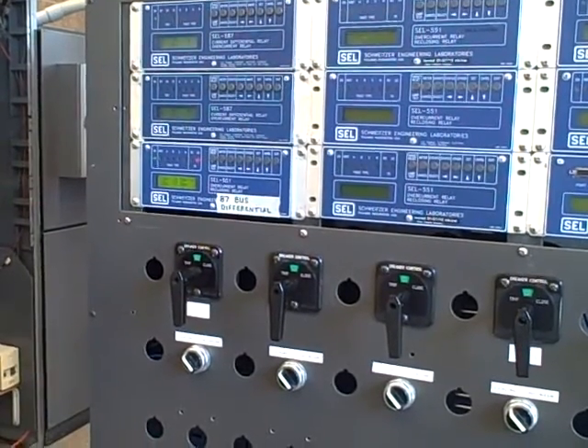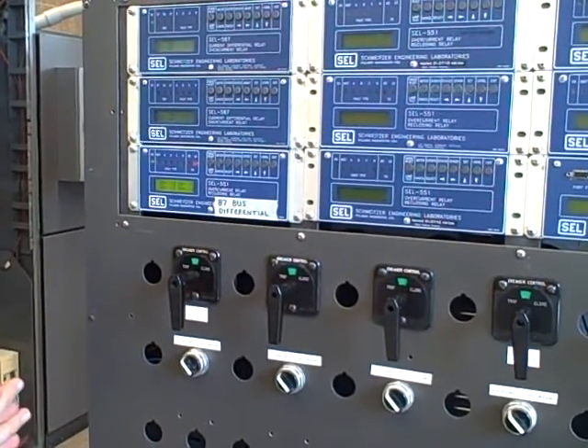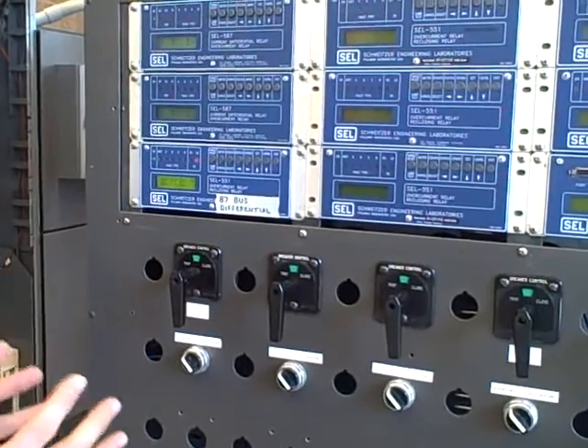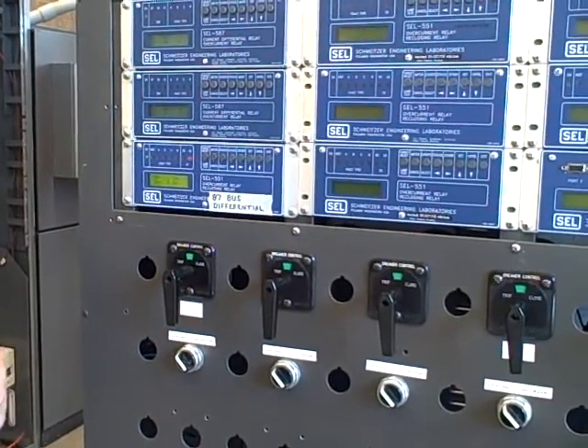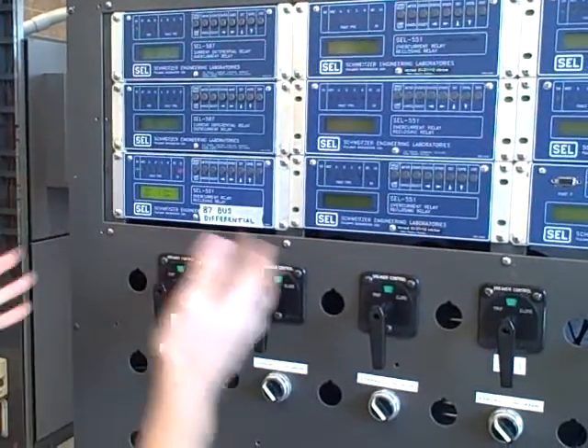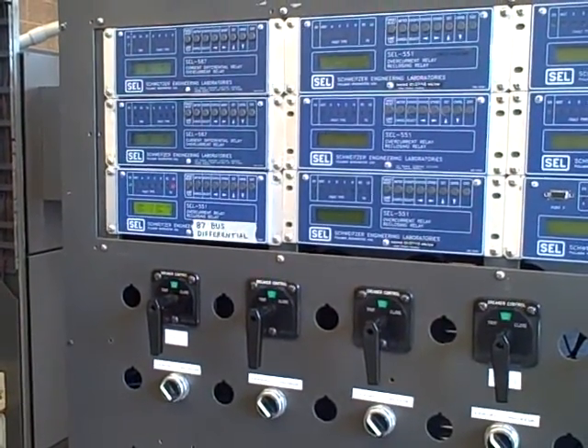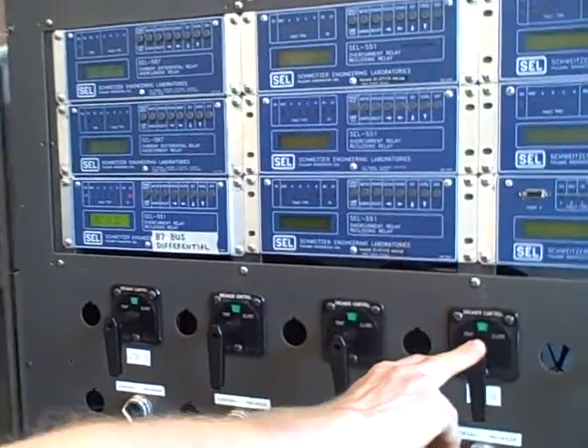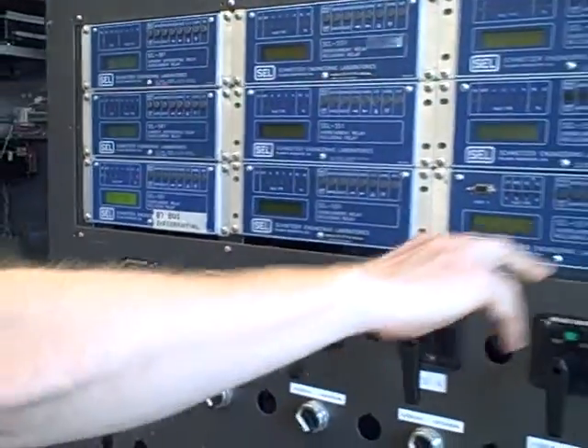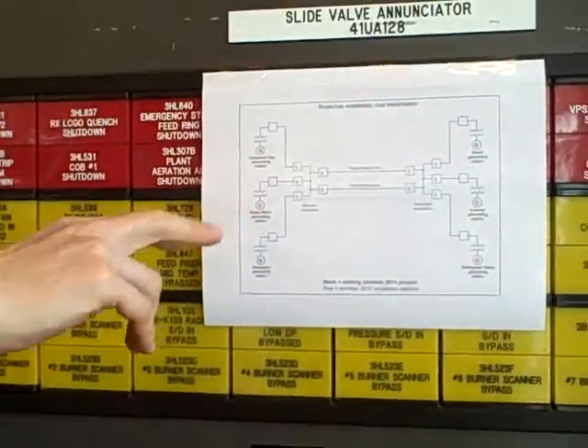We'll demonstrate this. We will introduce the fault to the system and hear the generator labor under that fault. Once the generator's breaker trips, we'll take a look at the 87 bus differential and see that it has not tripped. First step: I'm going to close breaker number four, which will connect the Diablo Miner generating station to our substation bus.